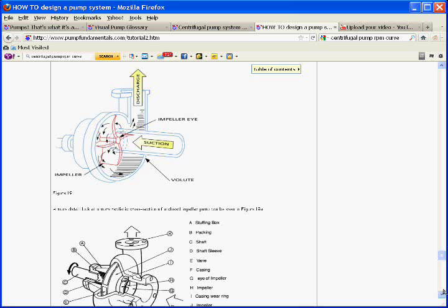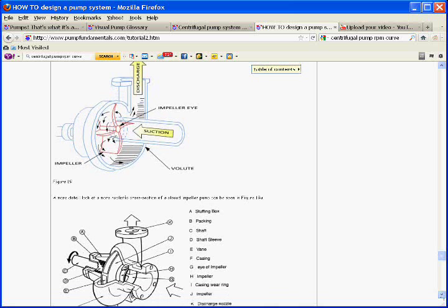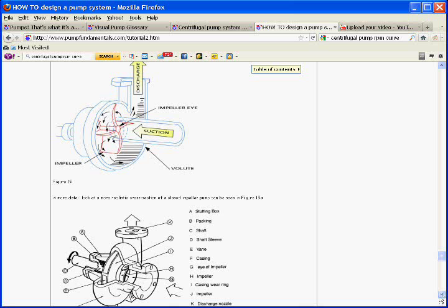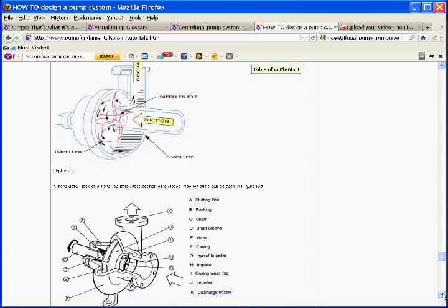You can see that here also. We're coming right in here. This is a closed impeller, so the liquid is constrained in this area between two impeller blades. The liquid's coming in, turns direction, is being rotated radially at high speed, comes into the casing. The casing has a bigger volume, so the velocity drops, pressure increases, and it goes out to the system.